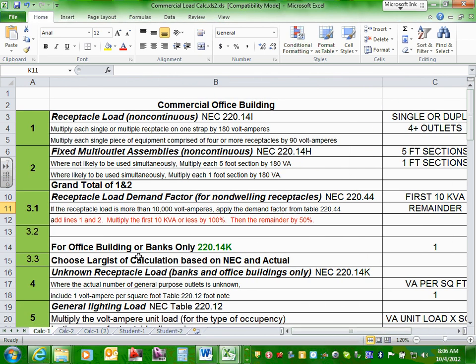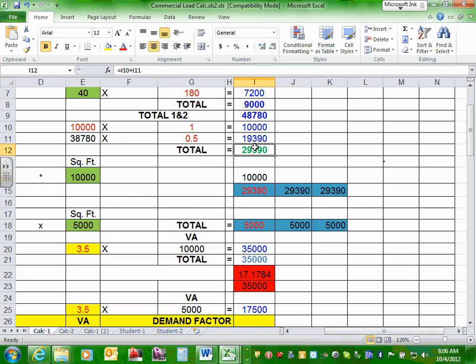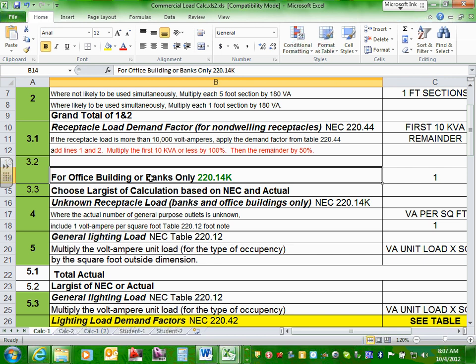Now because we're dealing with an office building — this is the most confusing part — the NEC code book says if you have an office building or banks only, you do the calculation we just did AND you do one volt-ampere per square foot, then choose the largest. Article 220.14(K) tells you: take 1 VA per square foot, multiply by the building square footage, compare with the rated volt-amps, and choose the largest.